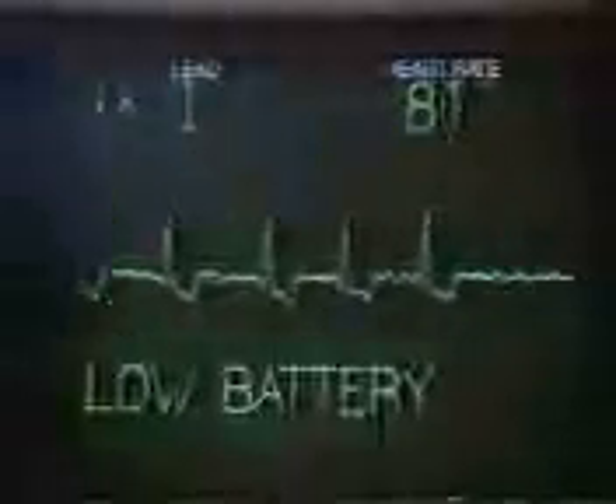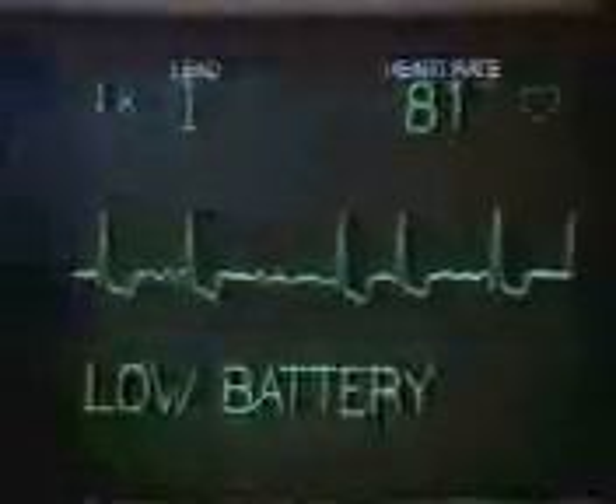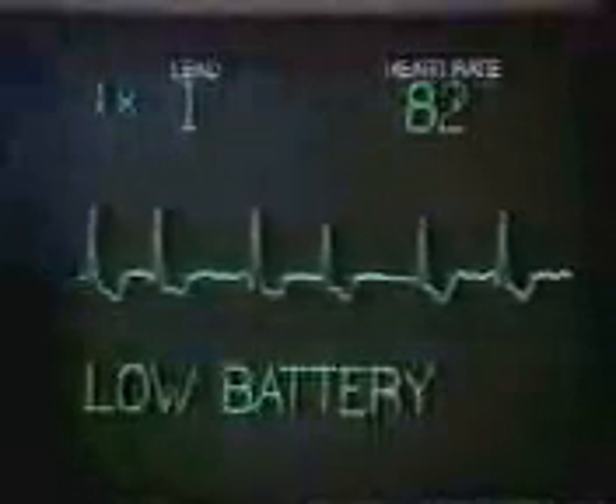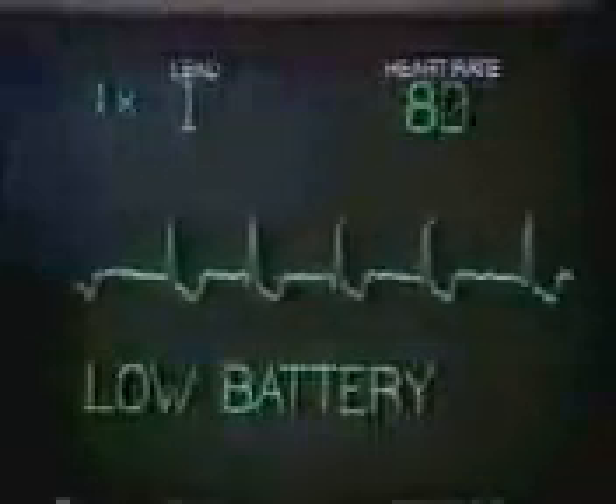The monitor on the ZOLL PD can be used for either short-term or long-term cardiac monitoring. For patient transport applications, the onboard battery supply provides up to 2 hours of continuous monitoring. A low battery message will appear when there is about 20 minutes of monitoring remaining, or 5 360 joules discharges.